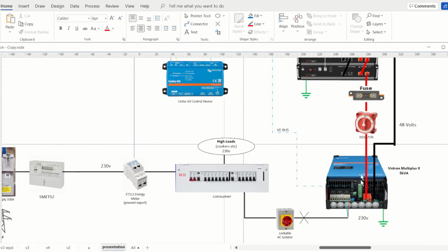Up to the capacity of the inverter, it will balance out, and whatever loads they are, you'll get the benefit of the energy storage. This is the simplest installation you can do, because you're not having to move wires around, separate your loads out, or worry about your loads exceeding the capacity of the inverter. Everything just works as is. You can put car chargers, whatever you like, hanging off of here, and this will support up to 20 amps. Effectively the input becomes the output, so it's bi-directional.